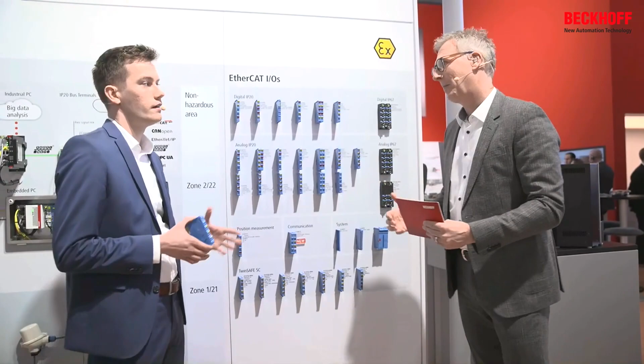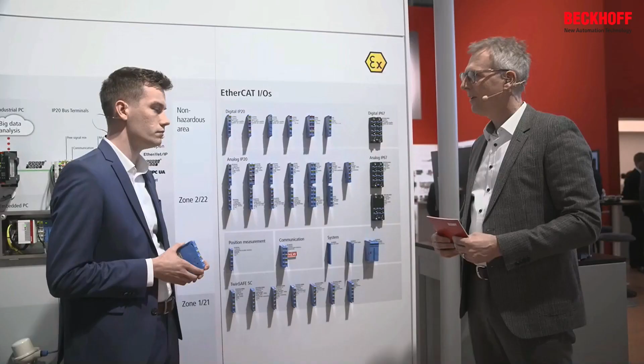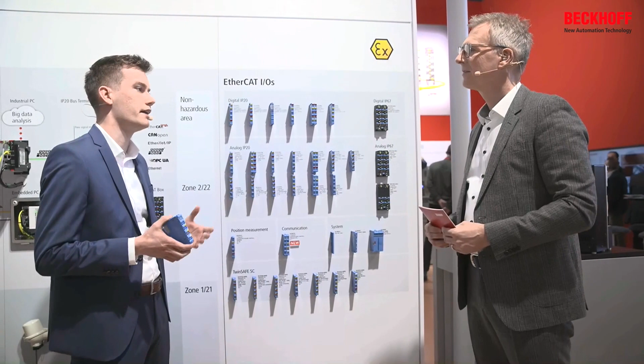What is Ethernet APL? So Ethernet APL is a new communication technology for the process industry. It's based on two standards. On the one hand, we have the Ethernet, the IEEE Ethernet standard, which is designed for the communication speed of 10 Mbits per second. We have a maximum cable length of 1 kilometer, and we do that all over just a single pair of cable. On the other hand, we have the explosion protection, which is an IEC norm. And this is designed for the intrinsically safe environment, and we use that over the same pair of cable to get the energy to the field devices.